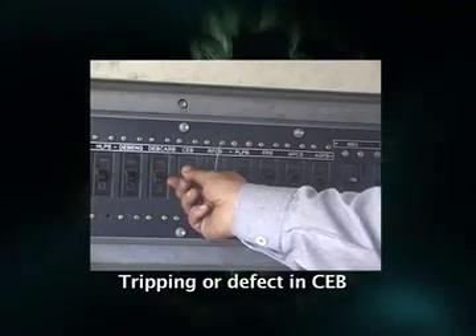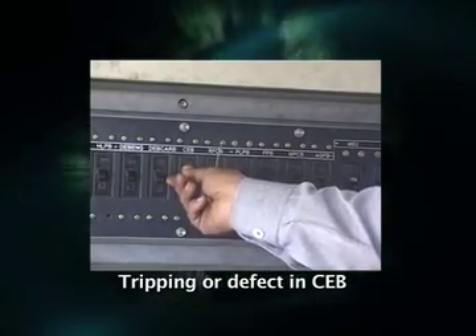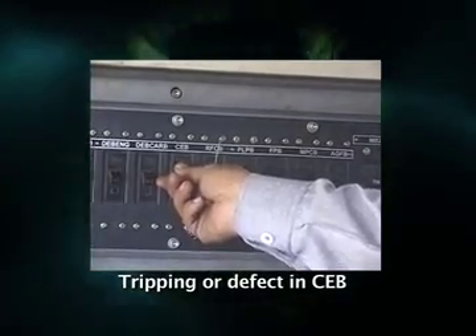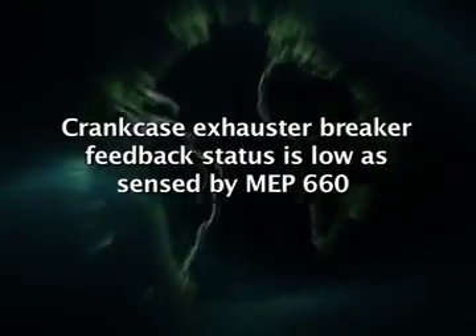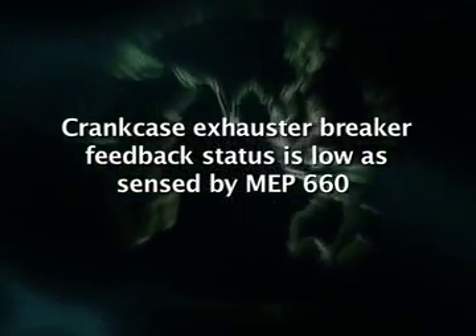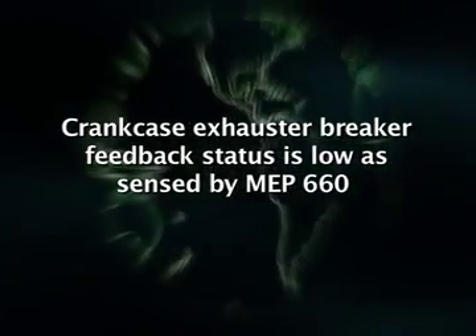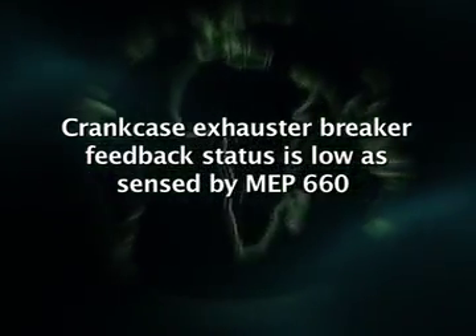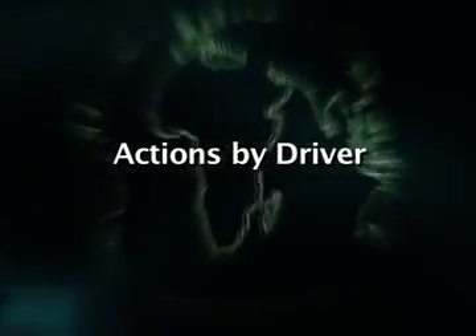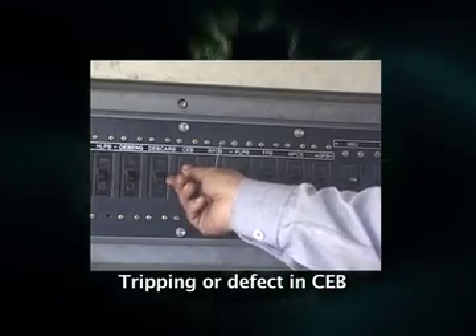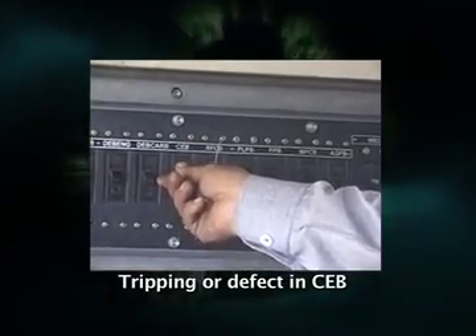Probable causes: tripping of CEB or defect in CEB. Defective wiring. Crankcase exhauster breaker feedback status is low as sensed by MEP 660. Action by driver. Tripping of CEB or defect in CEB.